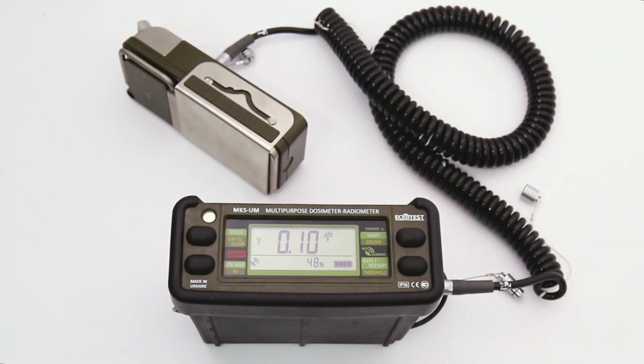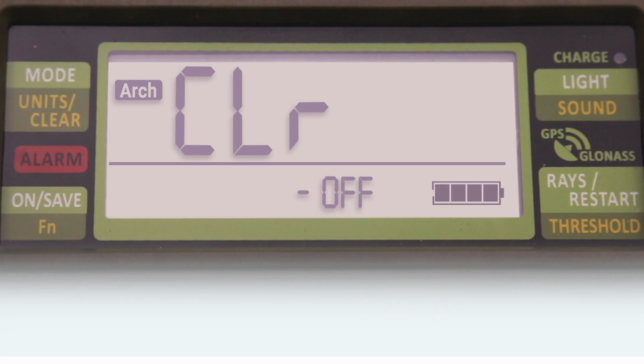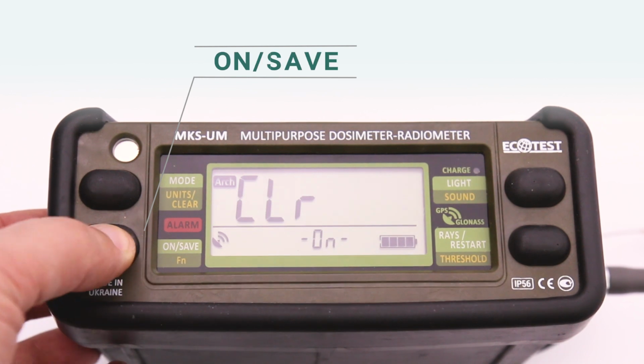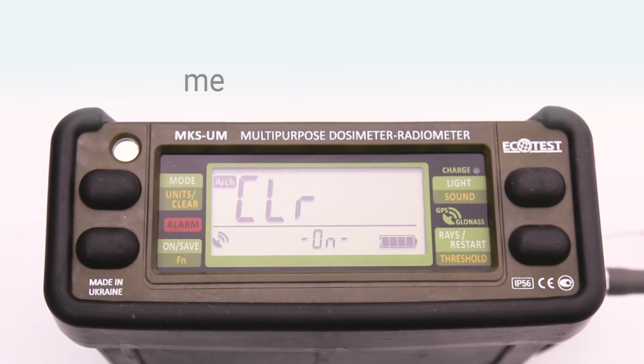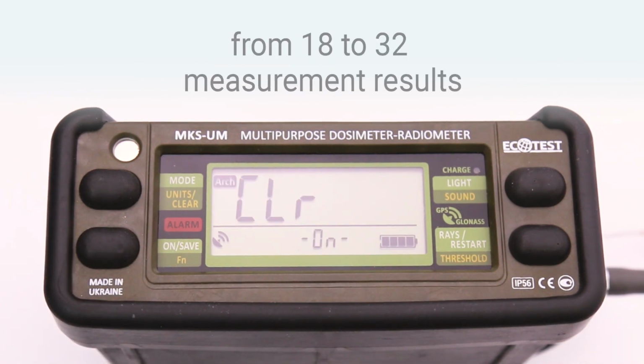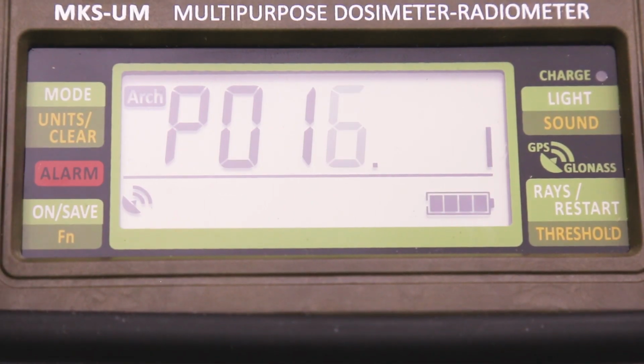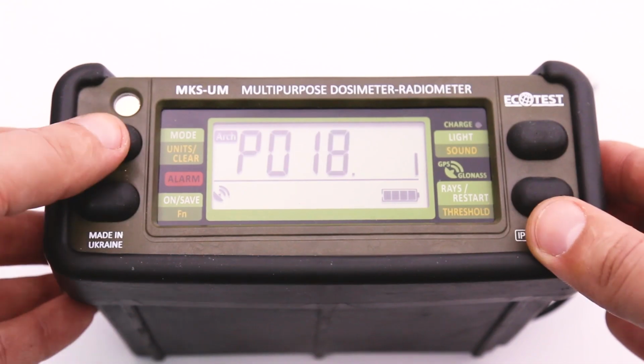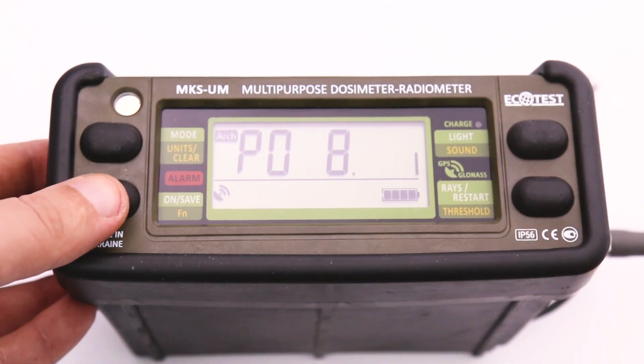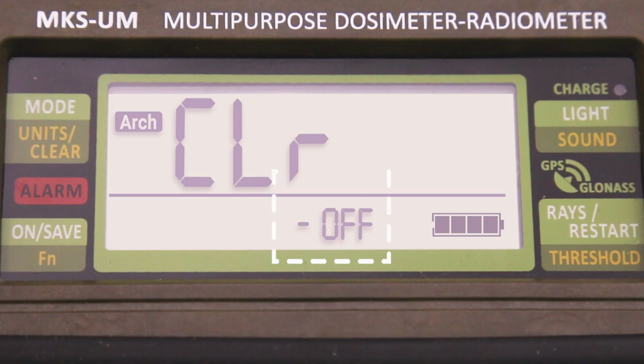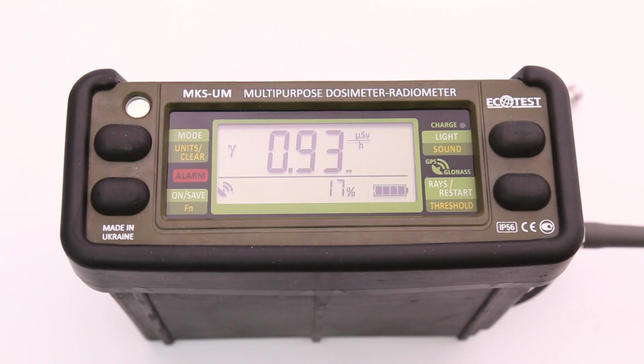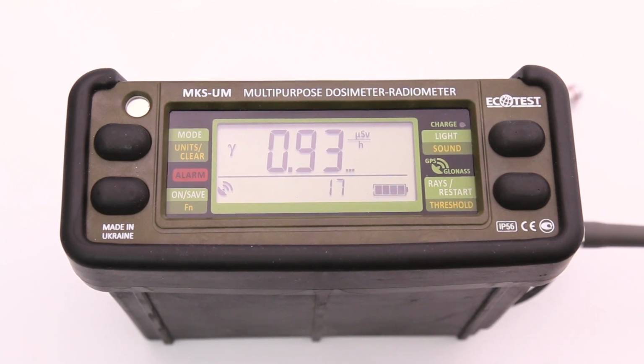When there is no free space in the memory before setting the object number, the control panel switches to the sub-mode of erasing the memory segment. Confirm the data erasing, and the device will erase from 18 to 32 of the oldest measurement results. And then it will switch to the sub-mode of setting the number of the measurement object. If you do not confirm the data erasing, the device will return to the mode of displaying the measurement results.